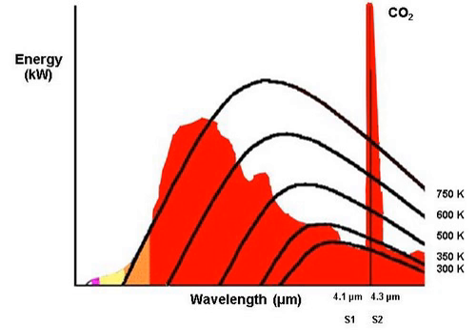Moreover, the cold CO2 in the air is taking care that the sunlight and other IR radiation is filtered. This makes the sensor in this frequency solar blind. However, sensitivity is not reduced by sunlight. By observing the flicker frequency of a fire, 1 to 20 Hz, the detector is made less sensitive to false alarms caused by heat radiation, for example caused by hot machinery.